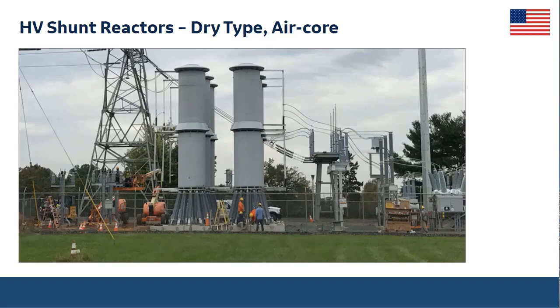Physically, they have similar sizes, but if we consider the magnetic field, yes, the dry type air core may require some extra space and clearances. But the message here is, if it's a greenfield, a new installation, most probably the air core dry type will be the best solution for voltages up to 500 kV. A typical installation has a breaker, switching device, grounding switch, the reactors, as we see in the pictures, and protection CTs and VTs. This is a typical installation, and I just wanted to show the picture to you.